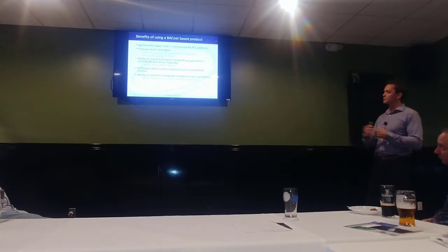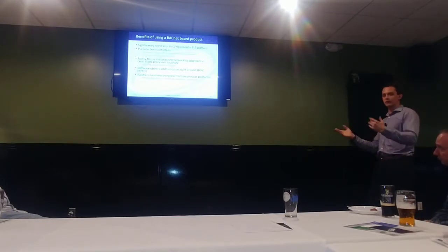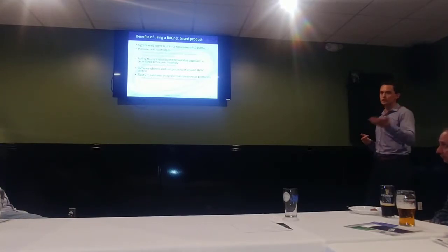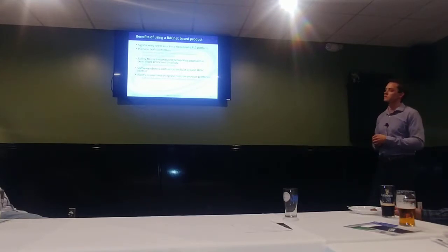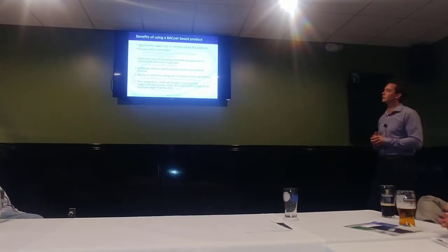Software objects and templates built around HVAC. We've all got control objects and special objects built into our controllers that are designed for HVAC. And then the ability to integrate multiple platforms. If you've got a PLC that doesn't natively speak BACnet or Modbus, you need to put translators in anyway to speak to your chillers, your boilers, your VFDs, those types of things. Next slide. So, last one.